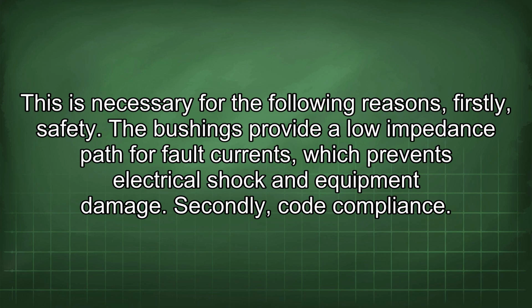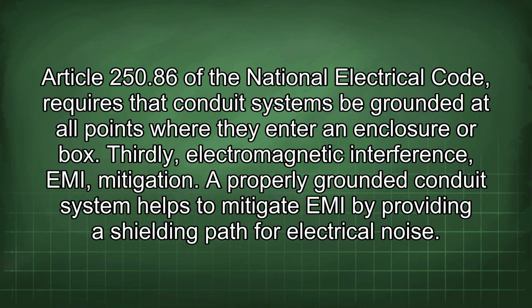Firstly, safety. The bushings provide a low impedance path for fault currents, which prevents electrical shock and equipment damage. Secondly, code compliance. Article 250.86 of the National Electrical Code requires that conduit systems be grounded at all points where they enter an enclosure or box. Thirdly, electromagnetic interference mitigation.